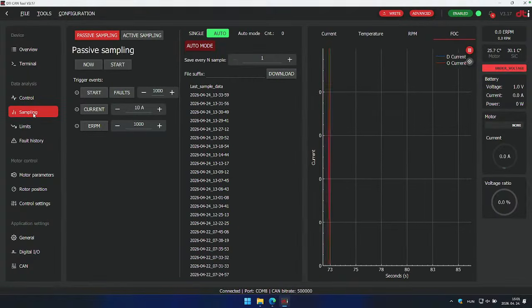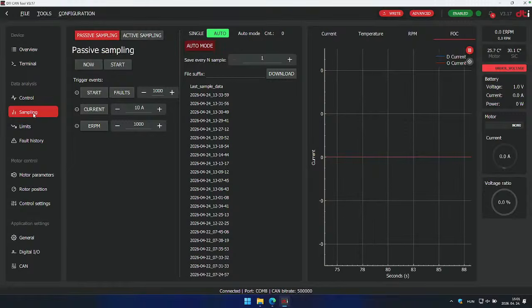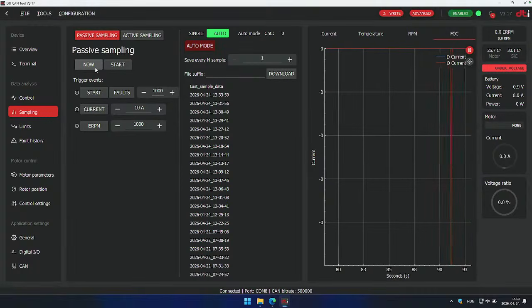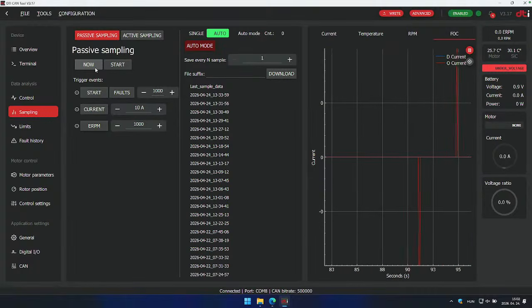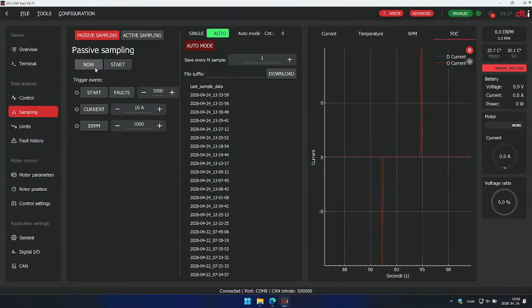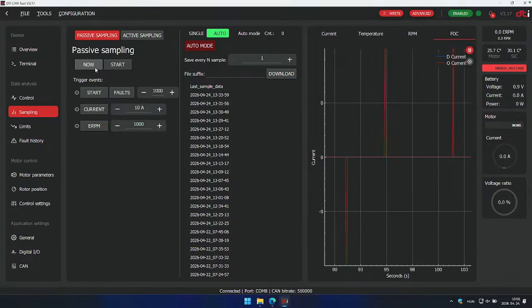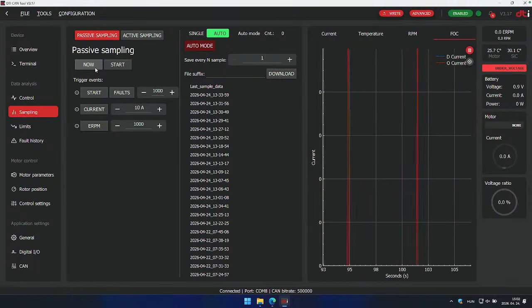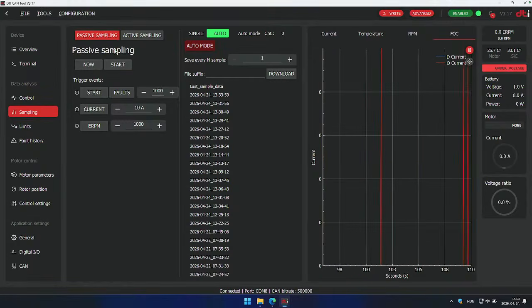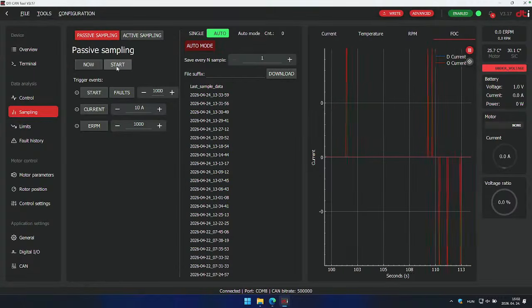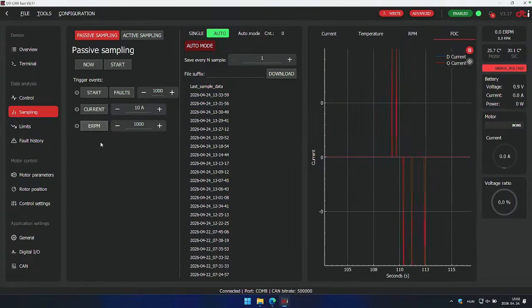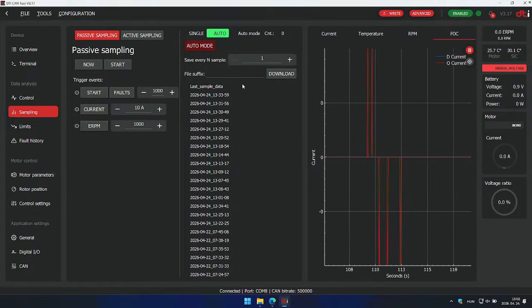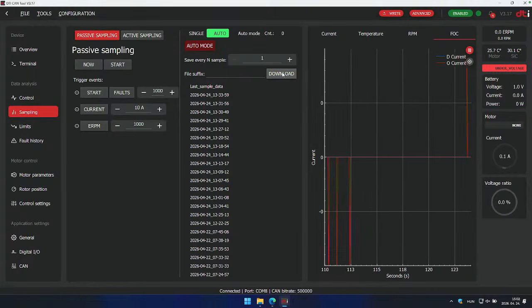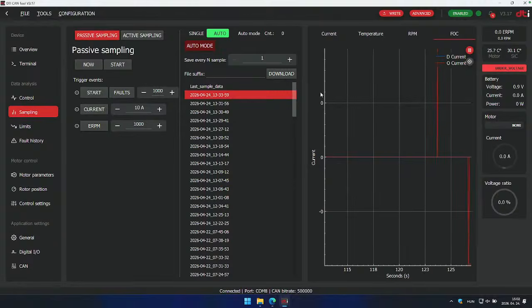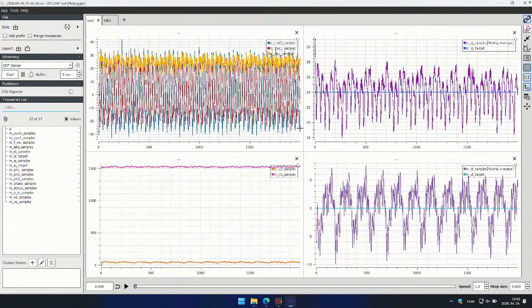We have sampling, a function which allows you to capture real-time data into the inverter's memory, sampled at the PWM frequency of the inverter, so it has lots of information involved. In passive sampling, you can capture data right now, when the motor starts, or at a specific trigger event you want. When this happens, you can download it from the inverter into the PC software and open it by clicking this file to see what's happening. I will show you in detail later.